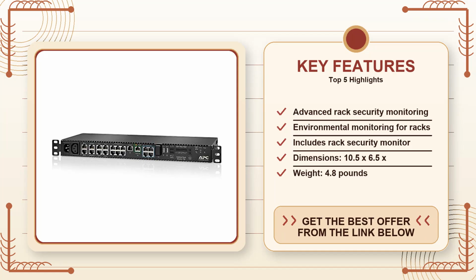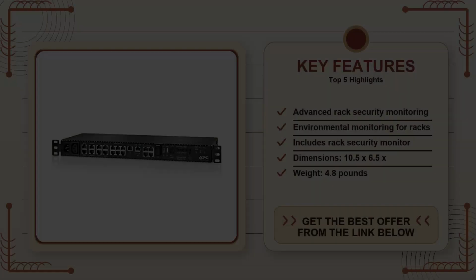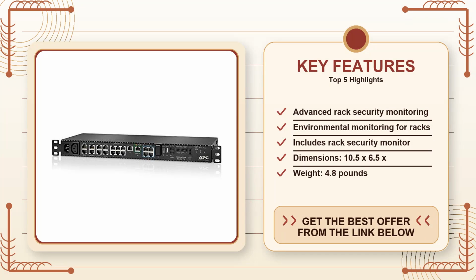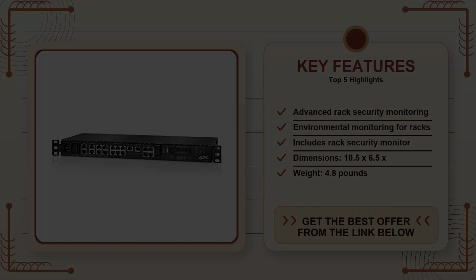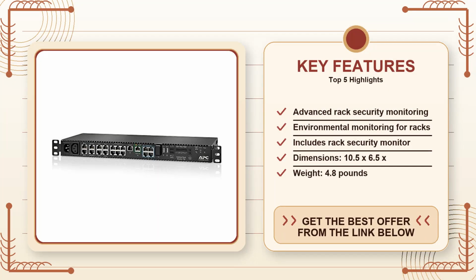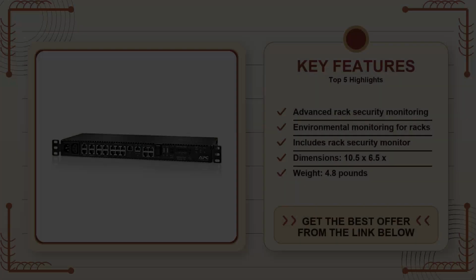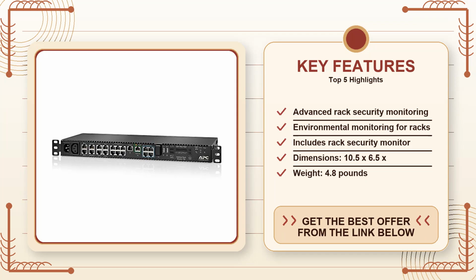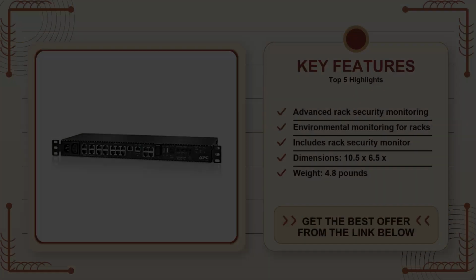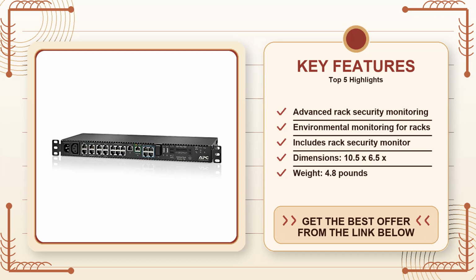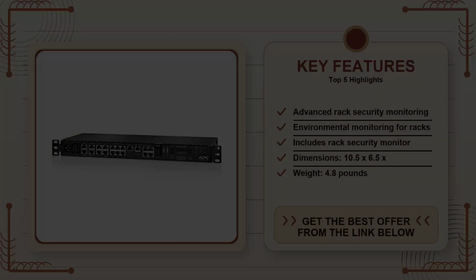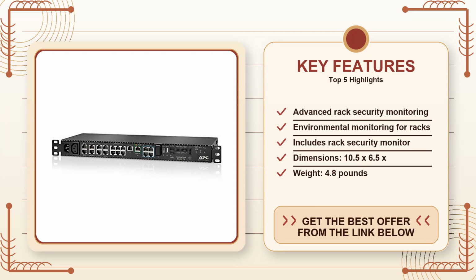One of the practical strengths of the NBRK0750 is the alert flexibility. You can set thresholds for temperature and humidity, choose whether you want an email, an SNMP trap, or a webhook call, and even create a hierarchy of alerts so a minor temperature rise triggers a warning, while a critical threshold triggers an emergency notification. This granularity prevents the alarm fatigue problem that plagues many monitoring systems where every little fluctuation drowns out the real emergencies.